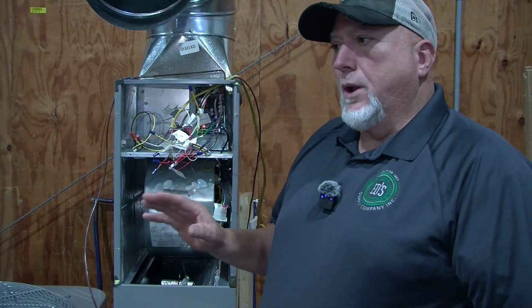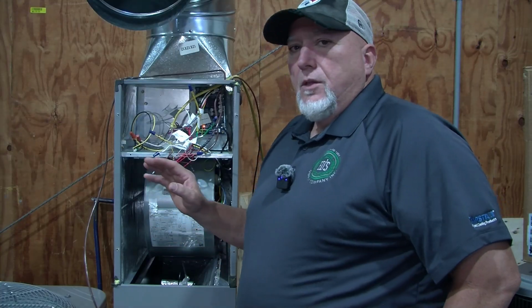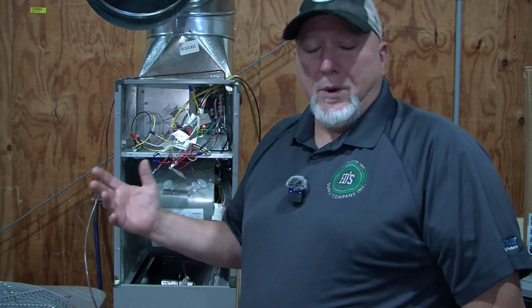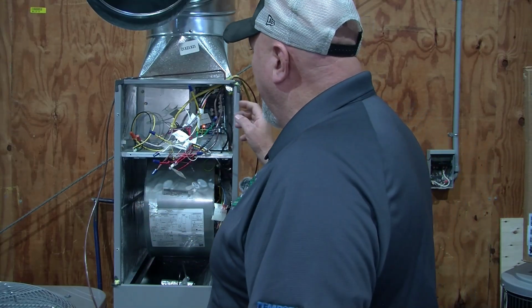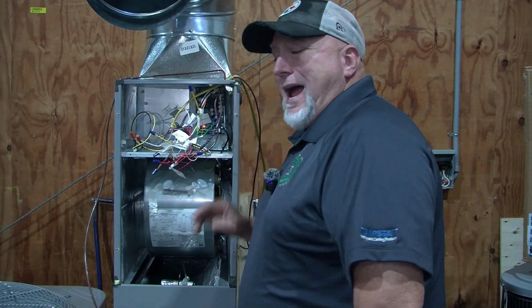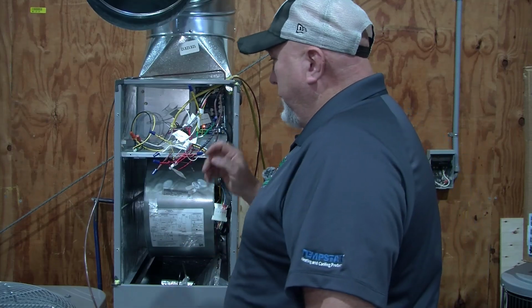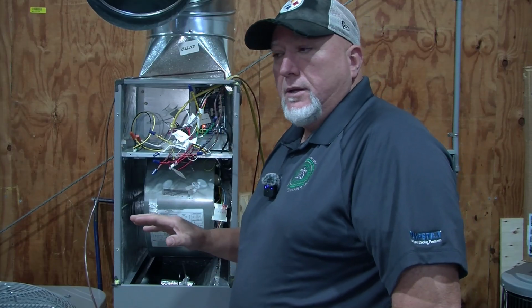Now, what I want to do is cover real quick the problems that we actually see going on in the field. And those problems are, if the amber light is on and the blower motor is not running, then it's waiting on a call to come on.